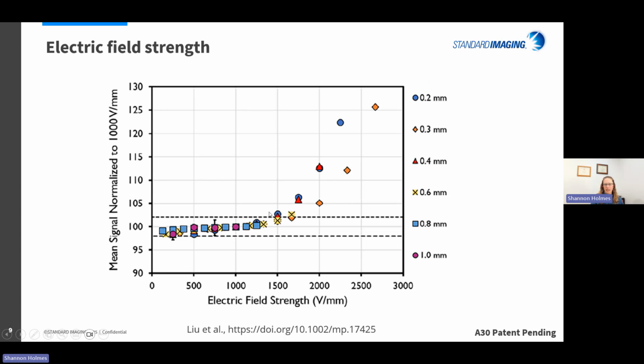And if you look at the electric field strength versus the signal normalized here to this 1,000 volts per millimeter electric field strength, once you get above 1,200 to 1,500 volts per millimeter, we start to move into the charge multiplication region of the ionization chambers. So you're creating a cascade rather than just collecting the ions that are generated by the irradiation itself. So we'd like to stay out of that region if we're going to stay in the calibratable region in terms of linking the signal to the dose.